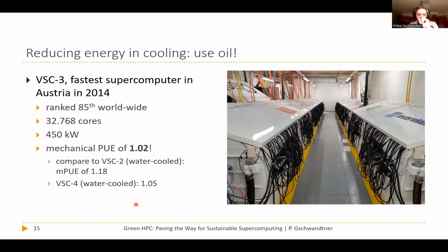There are a couple of reasons why the system isn't special at all. It's not special because when they built it, it ranked 85th worldwide in the Top 500 - there were 84 systems that were faster. It's also not special because it used almost 33,000 cores - there are many systems larger than that - and 450 kilowatts of power draw, with systems both above and below that. What was special and interesting was the power usage effectiveness of 1.02, which is really, really efficient, compared to the VSC2, the predecessor system which was water-cooled, at 1.18, which is worse, and the successor system at 1.05, which is also worse.